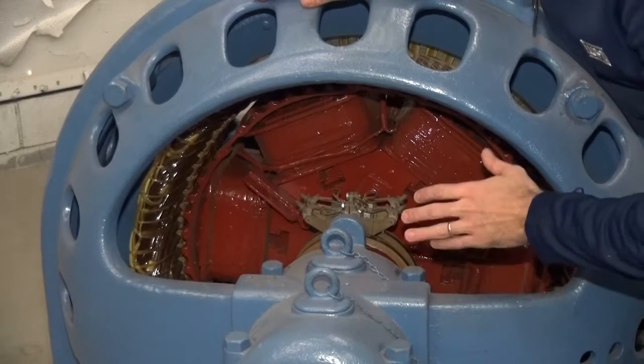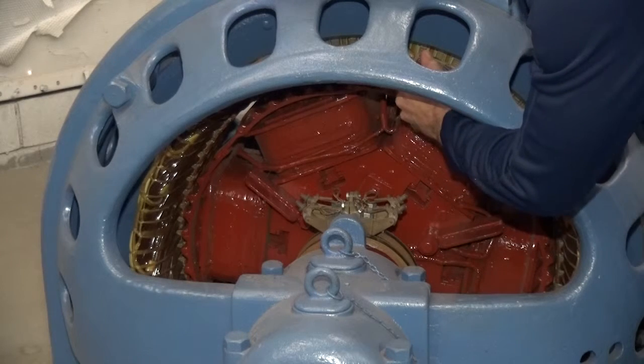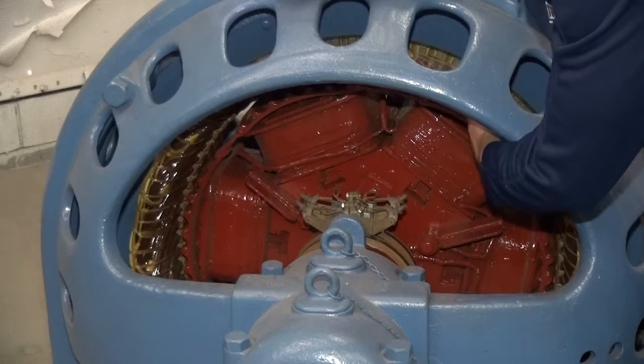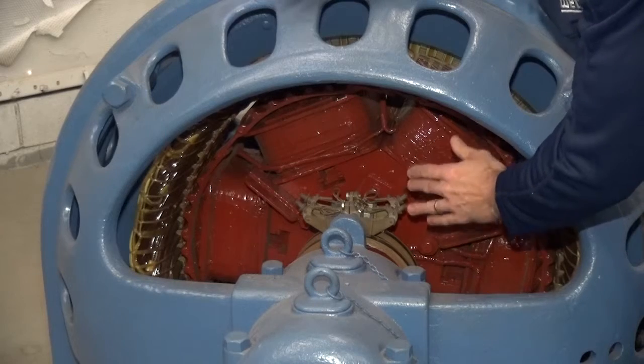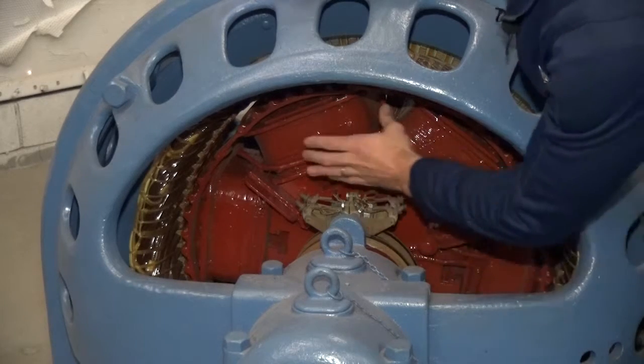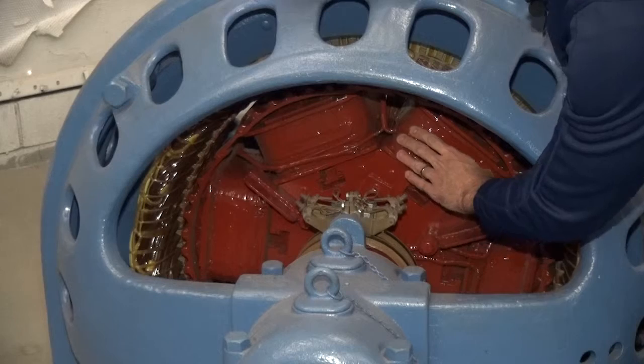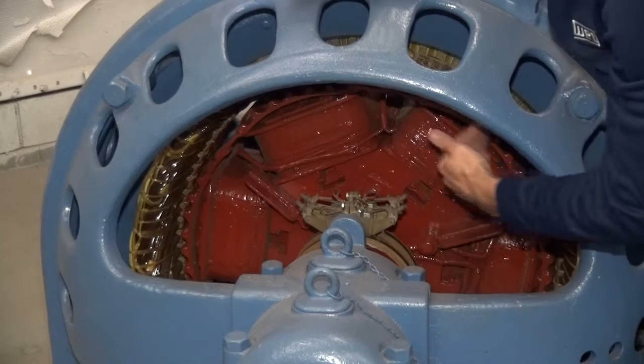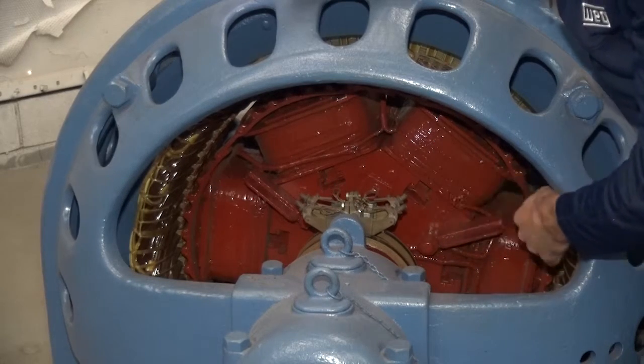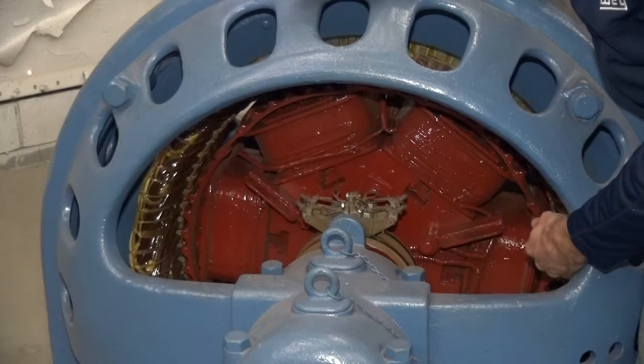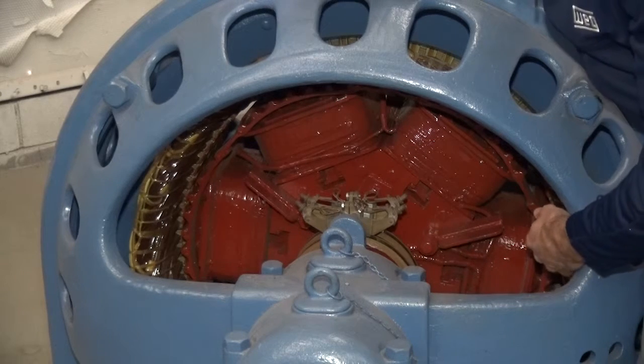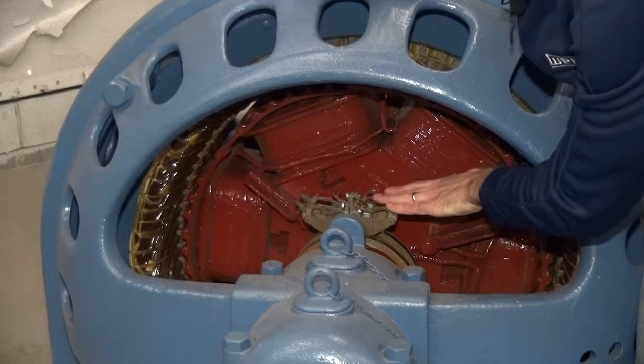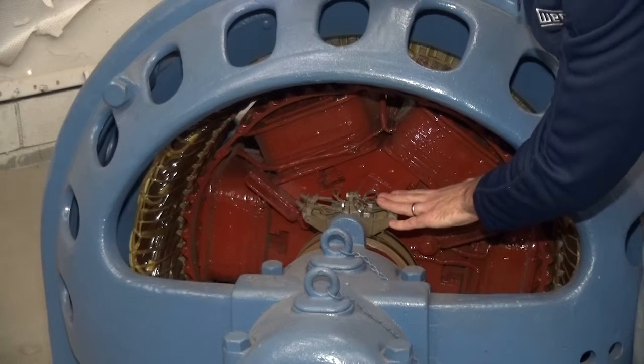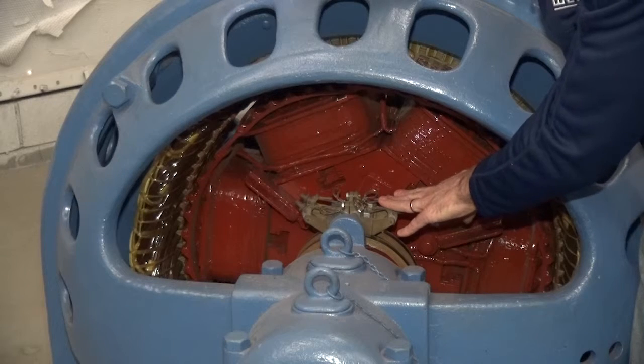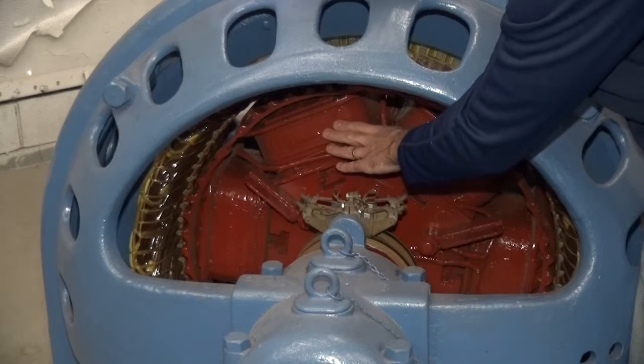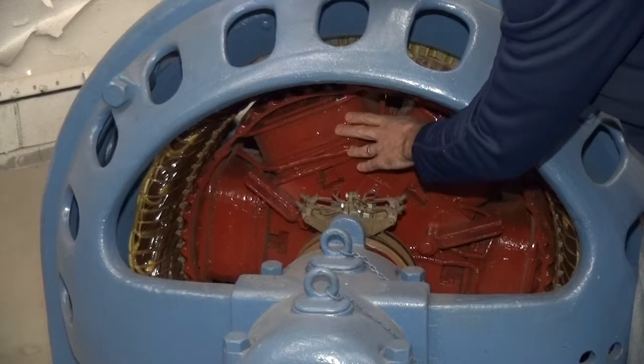Now we can take a detailed look at the assembly. You can see that this stator is a random wound stator, which is unique to this specific motor, which is used for training purposes. You can see the individual rotor poles, often called salient poles, and this machine has 6 poles. Obviously, it's a 6-pole motor, so it will operate at 1200 RPM in the North American grid. You can see that this is a collector ring motor, or it's statically excited. This is in contrast to a brushlessly excited motor, but the rotor poles operate the same in either.